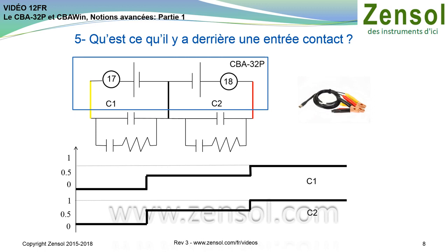Finally, it's easy to know exactly when the circuit breaker changes state, and we can then analyze the evolution of the contacts in relation to each other. It's this comparison exercise that's at the heart of synchronization. It is important to know that the CBA-32P is factory preset for two reasons. The first is to protect the instrument against high-frequency noise, while the second is to enable you to see digital and clear signals. In fact, substations up to 735 kV produce high-voltage electrical and electromagnetic induction, especially near lines with so-called live voltages.